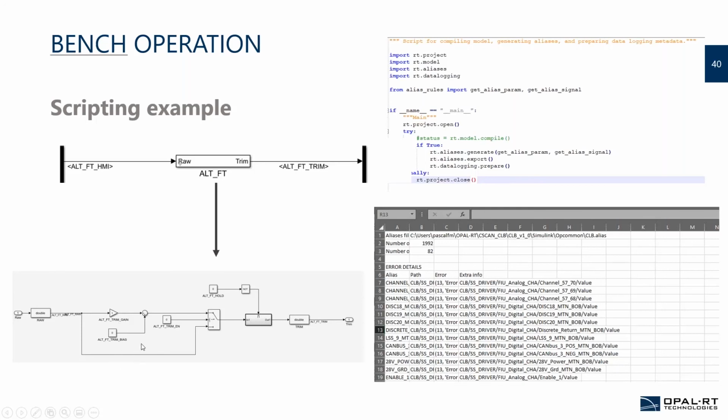Now it gives you values automatically as calibration, and this could be called by a script if needed, or from a timetable or exporting. So we can do a lot of things in there. It also gives you a way to either use what's going in, getting the input, calibrating, and getting out, or you can bypass it and force a value. So you disconnect the input and manually input a false value. It's a way to test and actually generate faults as well.